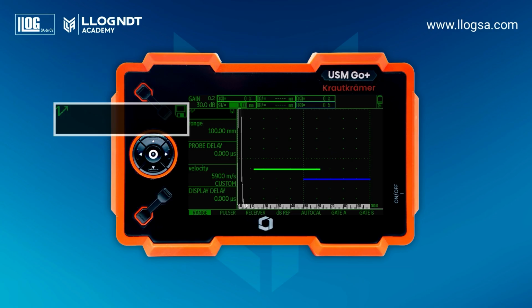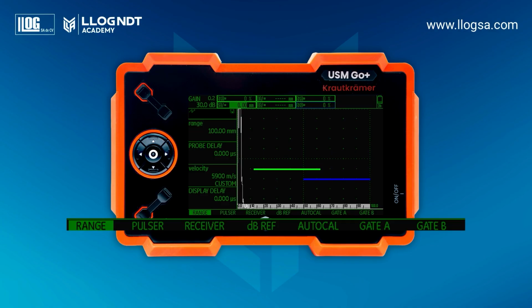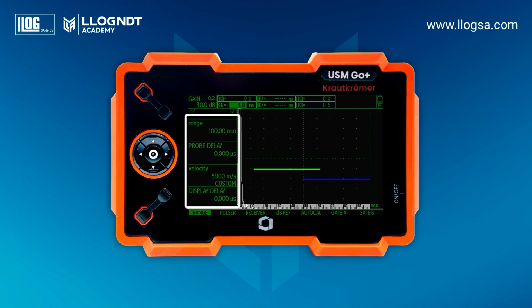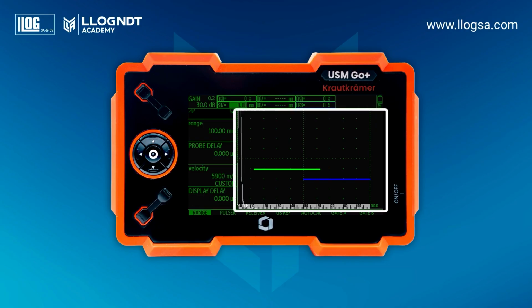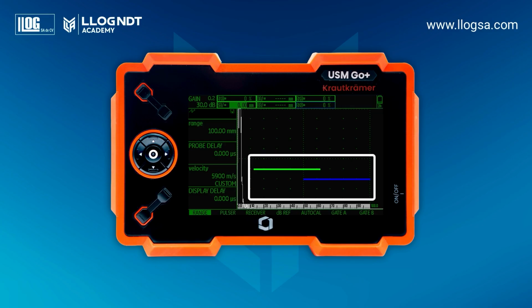Below that, you'll see the icon indicating the operating mode of the transmit-receive connectors and the icon showing that an SD card is inserted. At the bottom of the display are the first-level function groups for configuration. The selected group is highlighted in green. On the left-hand side, the functions corresponding to each group are shown. And finally, in the center, we have the A-scan. The horizontal scale represents distance or time, and the vertical scale represents amplitude in percentage. There are 2 independent gates that perform measurements of the corresponding echo.